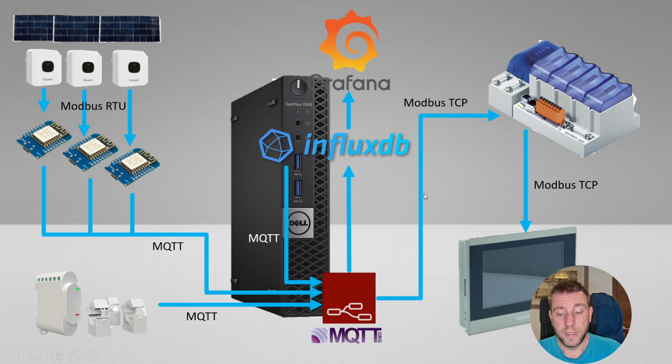And then finally, the display part of it is a Riectech HMI, a 7-inch touch panel. That again communicates to the PLC using Modbus TCP. I've just specified what addresses it needs to read and how it should display on the screen, like whether it's a signed or unsigned value, whether it has any decimal places or not. But that's pretty much it.